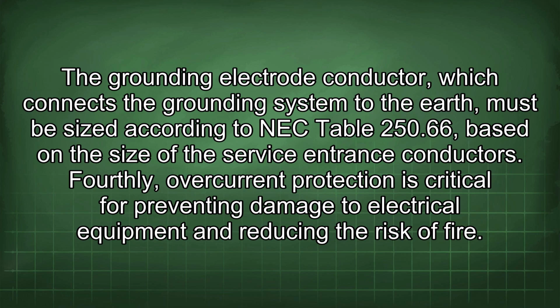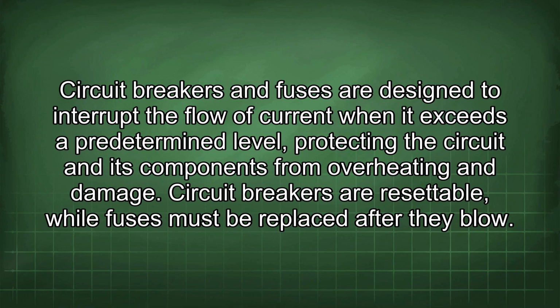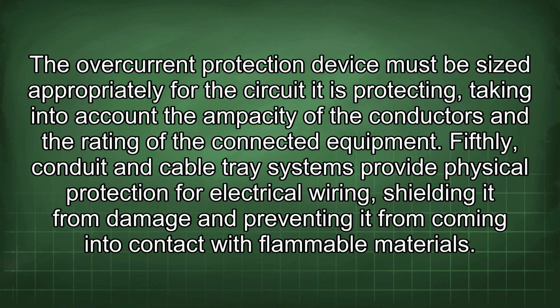The grounding electrode conductor, which connects the grounding system to the earth, must be sized according to NEC Table 250.66, based on the size of the service entrance conductors. Fourthly, overcurrent protection is critical for preventing damage to electrical equipment and reducing the risk of fire. Circuit breakers and fuses are designed to interrupt the flow of current when it exceeds a predetermined level, protecting the circuit and its components from overheating and damage. Circuit breakers are resettable, while fuses must be replaced after they blow. The overcurrent protection device must be sized appropriately for the circuit it is protecting, taking into account the ampacity of the conductors and the rating of the connected equipment.